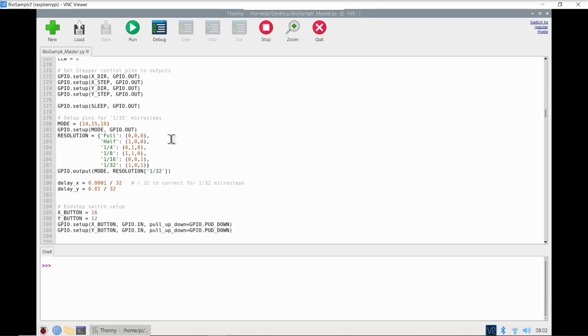We then set our step resolution. For the stepper motors we are currently using, they have 200 steps per revolution, and each of those steps can be broken down further into fractions of a step. We are using the microstep resolution, so each of those 200 steps is broken into 32 individual steps. This allows the motors to turn very smoothly — they are quieter and generate less heat, though they do have a little bit less torque. For our application we don't need a lot of power, and it also gives higher resolution and finer control over moving the sample needle to the sample tubes.